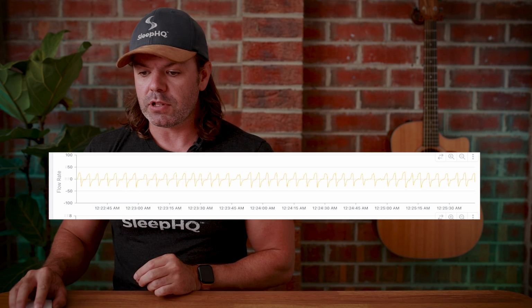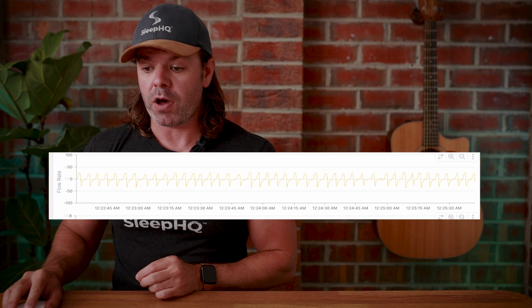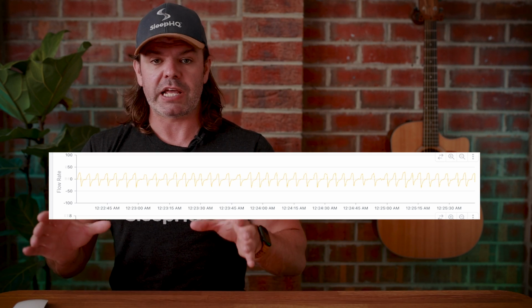Now, it's not perfect because remember, even though it's low, it's only 4 centimeters of pressure, it's still some pressure, it's still providing some therapy. But that's what I'd do first. If I wasn't going to do a sleep test, I'd drop my pressure down to the lowest level, import the data. Now, if the data looks like this, the flow rate, you're breathing throughout the whole night, it's good, even, stable breathing throughout the whole night, I'd then spend a night without the CPAP.